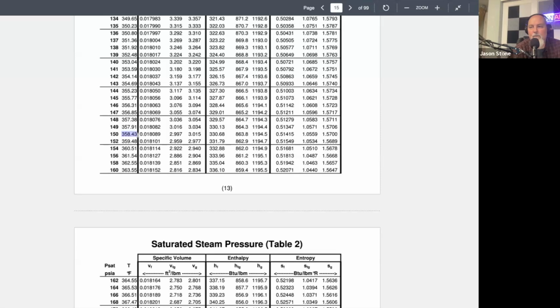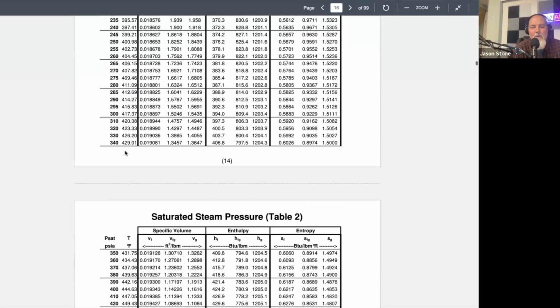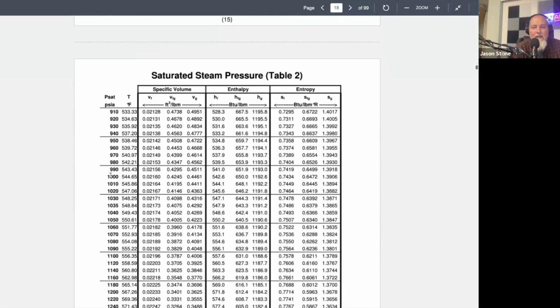So the 500 is the pressure, right? PSIA. No, if you look at number 11, it says 500 degrees Fahrenheit at 150 pounds of pressure. Oh, gotcha. And we always care what the pressure is. If you're going to figure out what the properties are, you look at the pressure. So number 12, for example, is at 1,000 pounds. So let's look at 1,000 pounds. And it says how many degrees of subcooling does water at 420 degrees Fahrenheit have? Well, it's this value minus 420 degrees Fahrenheit.